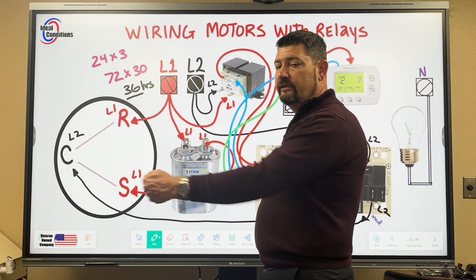And anything past that minute, basically, the coil is almost at a room temperature at that point. But because the temperature of that coil is either warmer or colder, depending on which mode it's in, okay, then the air moving across it, you are still transferring heat. Okay, now the heat's not being transferred to the outside unit, or vice versa, but it is collecting on a warm surface to the air, or from the warm air, warm moist air if you're in Florida, to a cold coil, which will condensate. And so you're getting dehumidification on that back end.